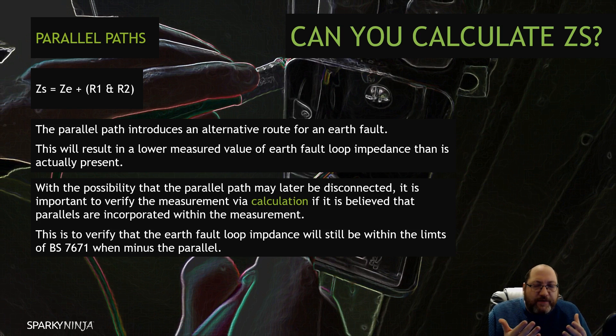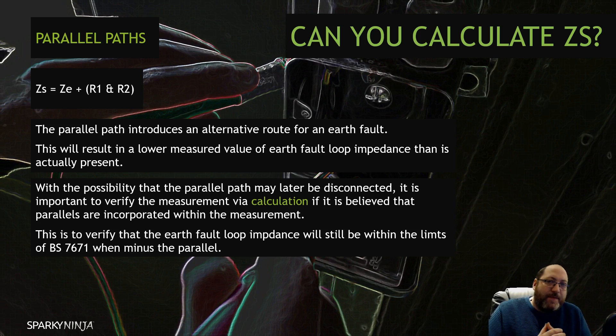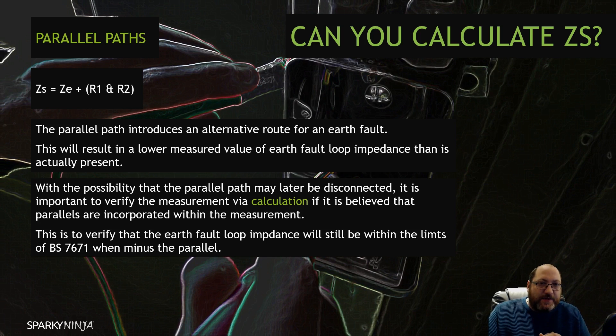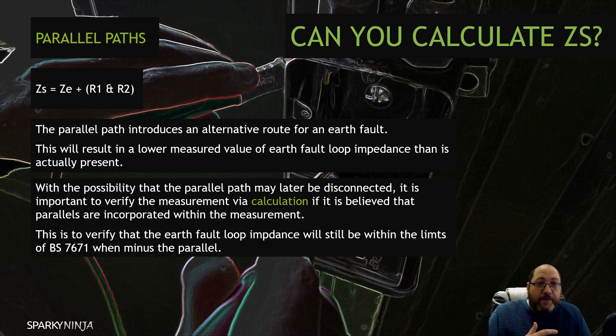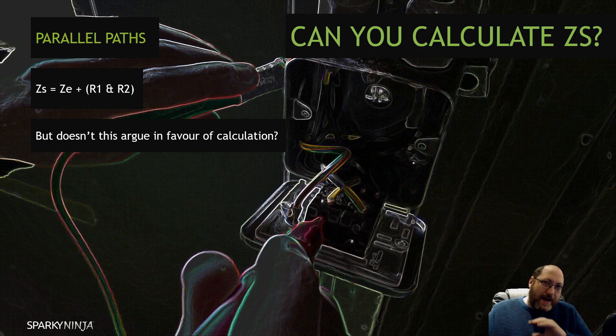If there's a fault here, some of the earth fault current will go one way and some will go the other — two parallel resistances. So a parallel path introduces an alternative route, resulting in a lower value of earth fault loop impedance than is actually present. Is that a good thing? Well, the thing is, what if that parallel disconnects later? If you've got an earth fault loop impedance that was expected to be just shy of the limit, but was way above it — you didn't know because the parallel brought it down — and then the pipework is changed to plastic, it could spike up. So if you're aware of parallels, it's important to also calculate the test, not instead of measuring, but to verify the ZS will be within regulation limits if the parallel were to disappear.